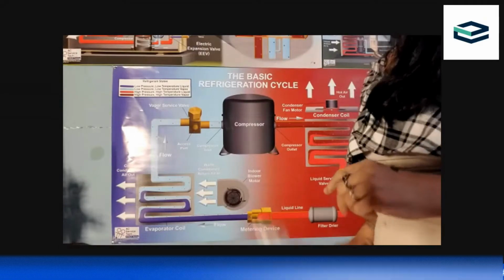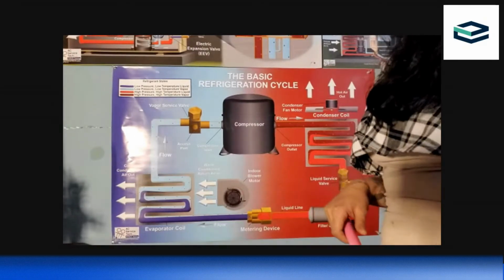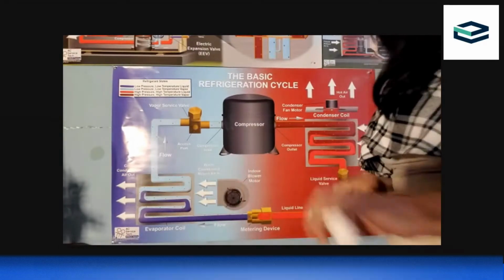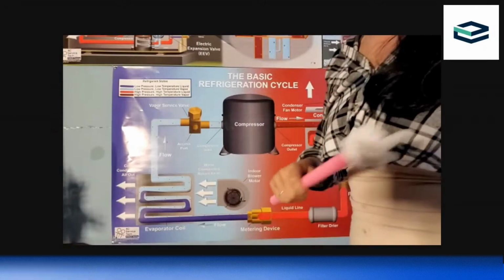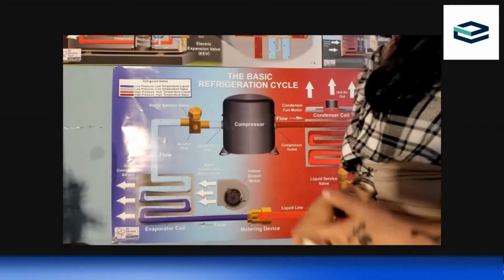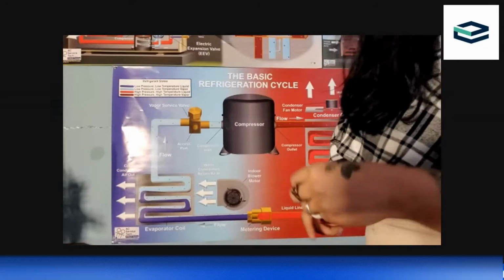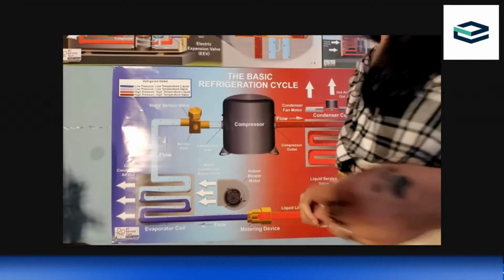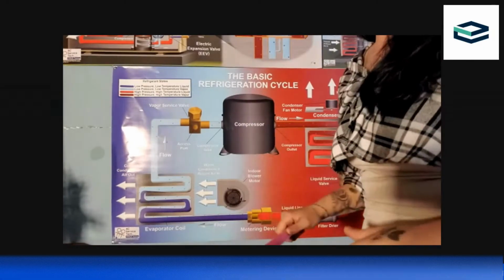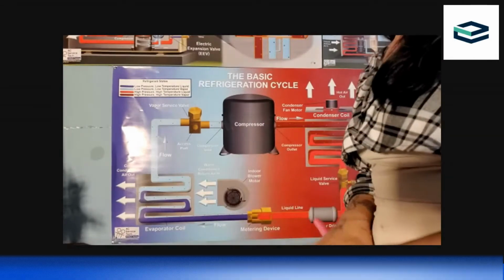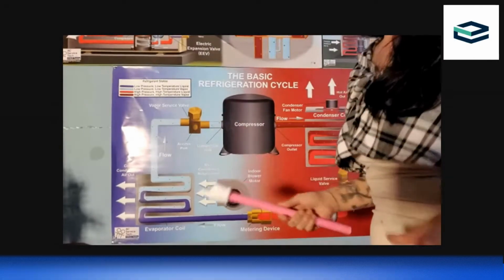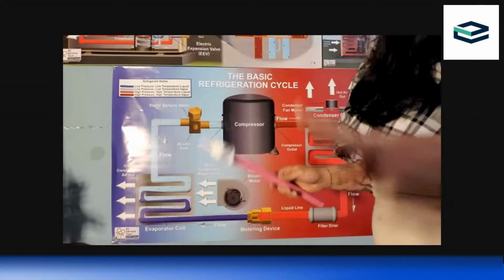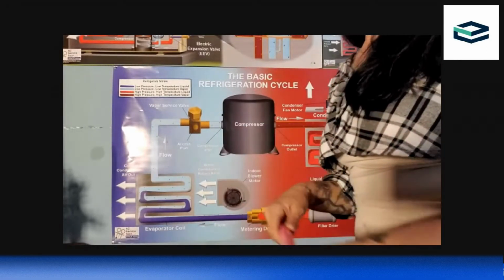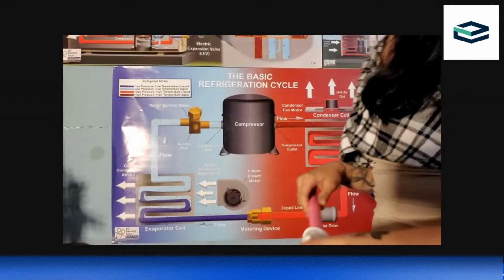There's a lot you can tell if your pressures are very low on both sides, or if one side is very, very high, one side is very, very low. You can tell that you may have a restriction, or you may be low on refrigerant, or you may be overcharged. But it's a point of access. It's not a be all end all. So what we don't learn about a lot, even in school, is the rest of those numbers that are on that screen. So what I'm going to teach you guys about now is a little bit about those other numbers.